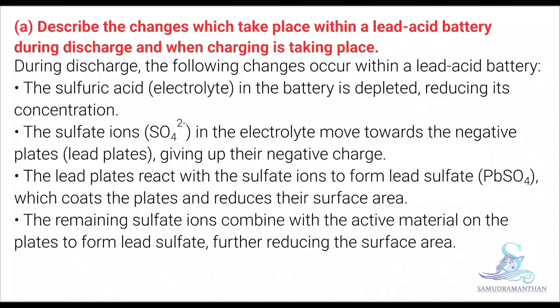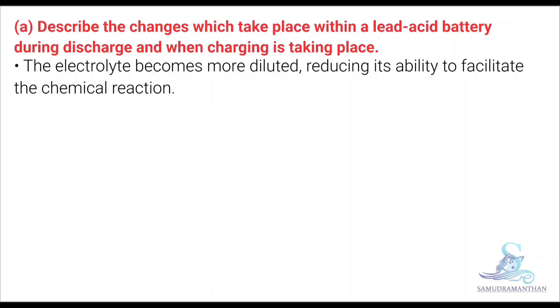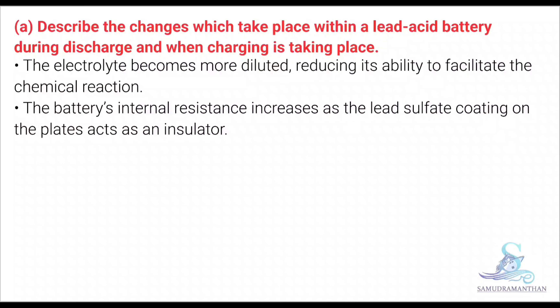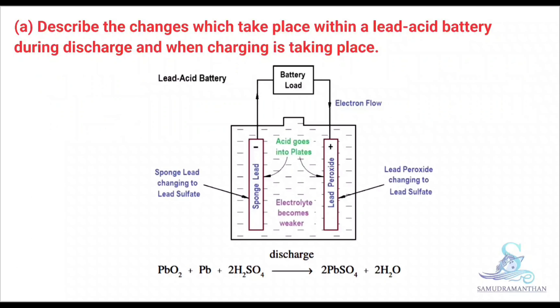The remaining sulphate ions combine with the active material on the plates to form lead sulphate, further reducing the surface area. The electrolyte becomes more diluted, reducing its ability to facilitate the chemical reaction. The battery's internal resistance increases as the lead sulphate coating on the plates acts as an insulator.